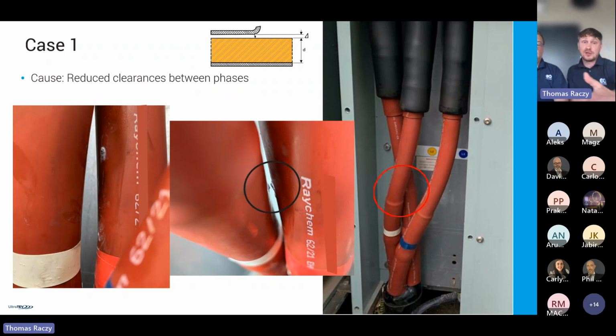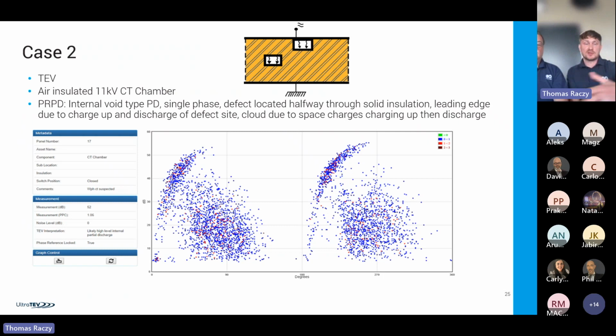And this is what was actually found on follow-up investigation. You can clearly see the lack of prescribed clearances between insulated conductors, and in that middle photo you can see a buildup of white oxides. That will continue to build up until it completely bridges, and there's going to be a complete phase-to-phase discharge.